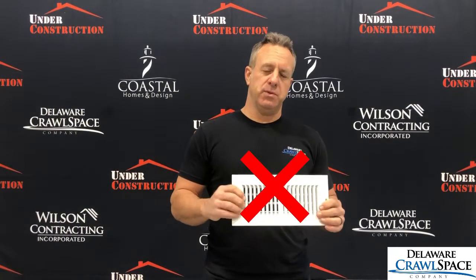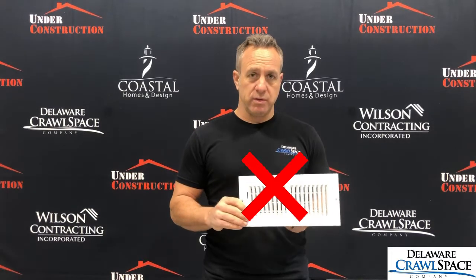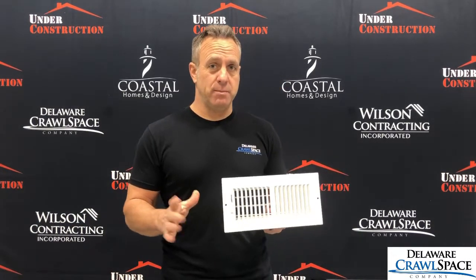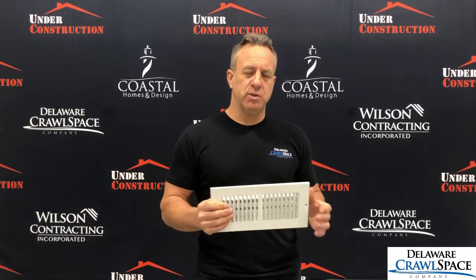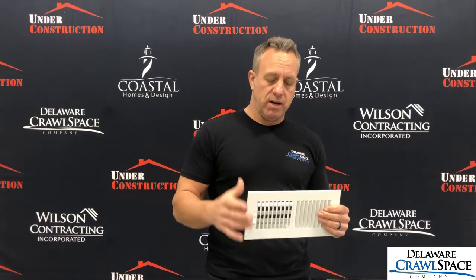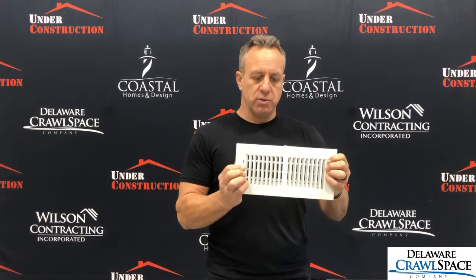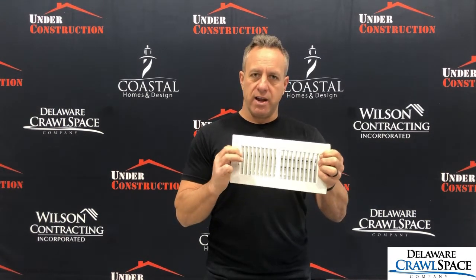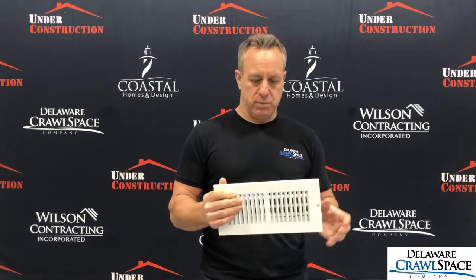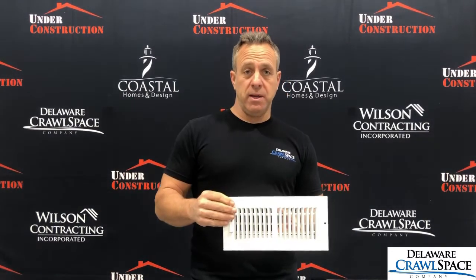So when we condition a crawl space, this is not what we use. This is what most people would do. You're going to probably see this on almost all jobs that are conditioned. They would cut a hole in the supply side of the ductwork, and they would basically just fasten one of these to the ductwork, and it just opens and closes just like a regular supply grill in your house, and you're just going to let air flow into the crawl space. This is not what we recommend. It's the cheapest option, although it still introduces that air into the crawl space that you need, but it's certainly not the best option for you.